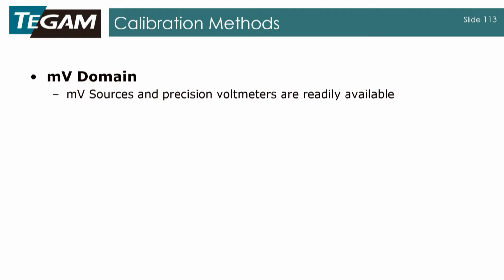So when you're calibrating temperature, though, you have three areas, three methods. One is in the millivolt domain. When you're calibrating both, say, thermocouples or RTDs and instrumentation, you can operate in basically the millivolt area. So you can get millivolt sources and really precision voltmeters, 8.5 digit DMMs. I think Fluke has a new one that they'll be showing out here on the show floor this week. I think it's the 8588. Of course, the 8508's one people used a lot, 3458. There are a lot of Waveteks that are still out there. Transmille makes one. But those are available, and you can measure a thermocouple, you can measure its absolute millivolt behavior, and then you can compare that to tables.